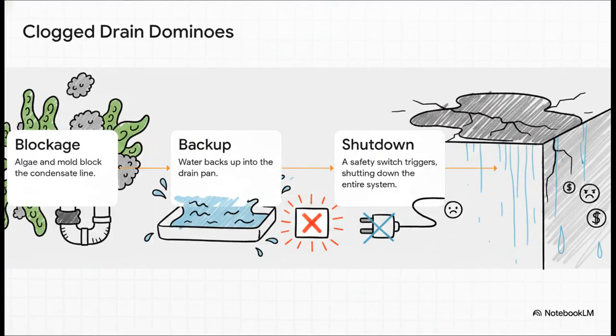This is a brilliant illustration of how one tiny problem can cascade into a disaster. First, some algae and mold block the condensate line. Seems simple, right? But then water starts backing up into the drain pan. Now a safety switch is supposed to trigger and shut the whole system down. But what if that little switch fails? Well, then you get an overflow, leading to thousands of dollars in ceiling and wall damage. A tiny clog becomes an absolute catastrophe.